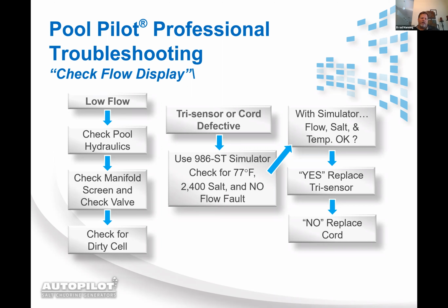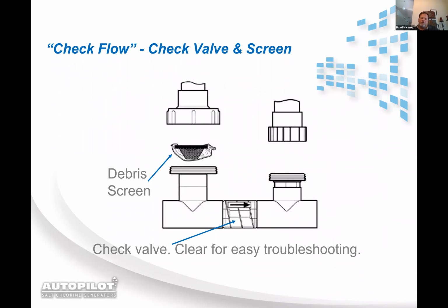Once you've checked all that, if you do have a stuck check valve, you need to wrap the debris screen in some plastic, close the manifold back up, and force all the water through the bottom manifold, and hopefully whatever debris has it stuck will blow through and allow the check valve to close again. If that check valve is stuck in the open area and you can't get it to close, then you're going to have to put in a new bottom manifold.